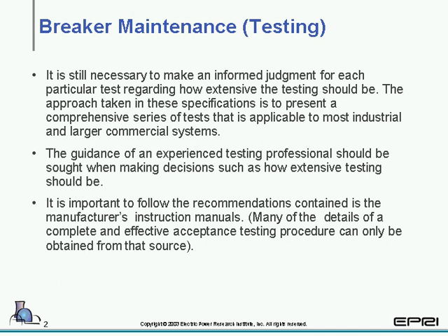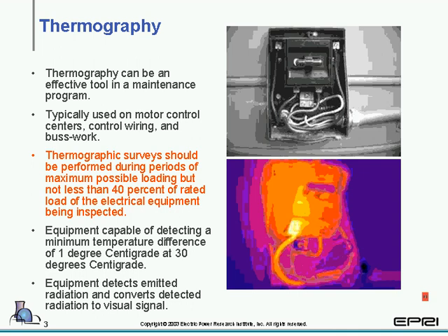We're going to look at Section 2, Part 5, the testing and test equipment. It is necessary to make informed judgments for each particular test regarding how and the extent of the testing that you're going to want to perform. You may want to consult an outside vendor and/or the manufacturer to come up with specific tests at your specific plant or in your specific situation that will, as said earlier, give you confidence that the equipment is not only in good shape as left, but will perform its intended function until you're ready to remove the equipment from service or overhaul it again. And keep in mind, common sense, along with the instruction manuals.